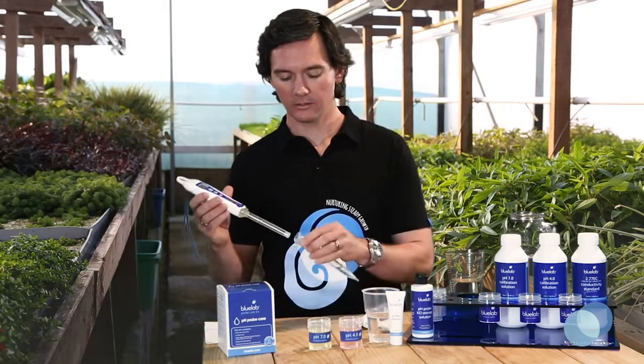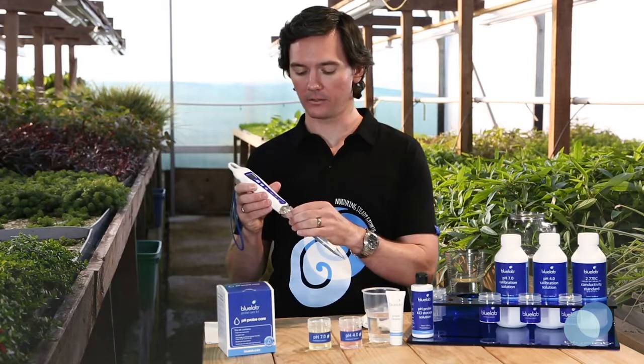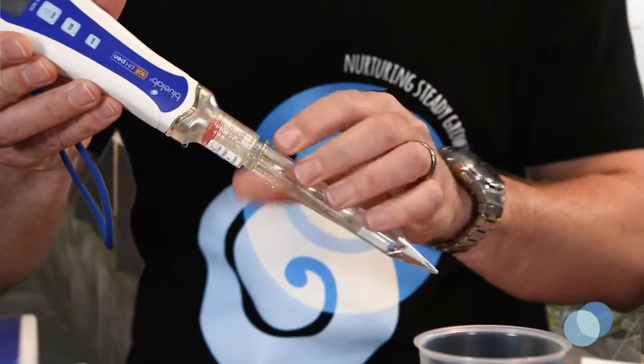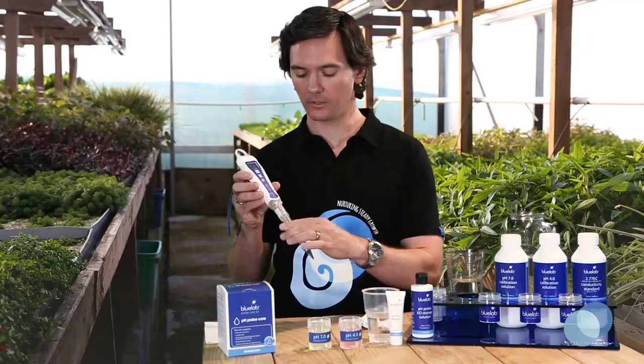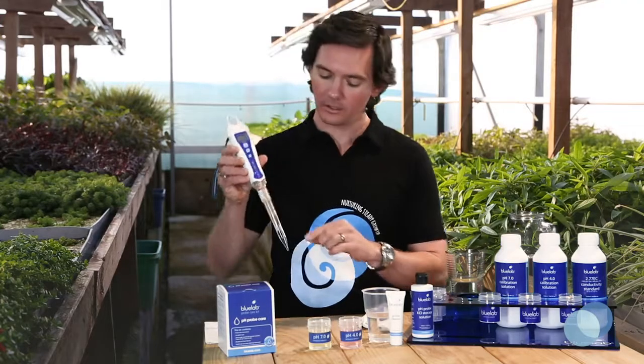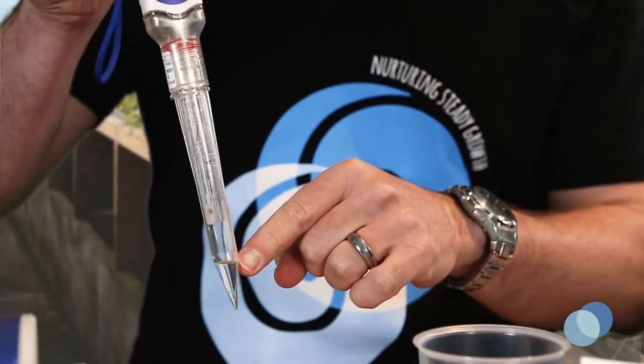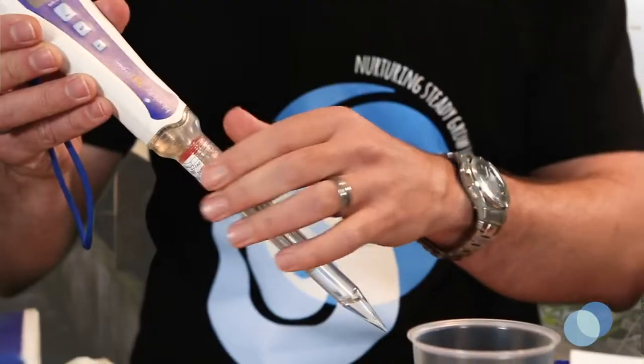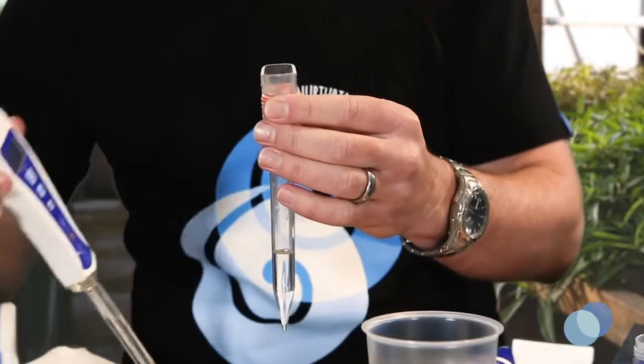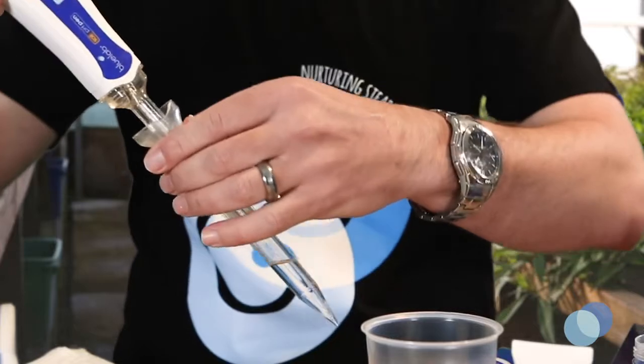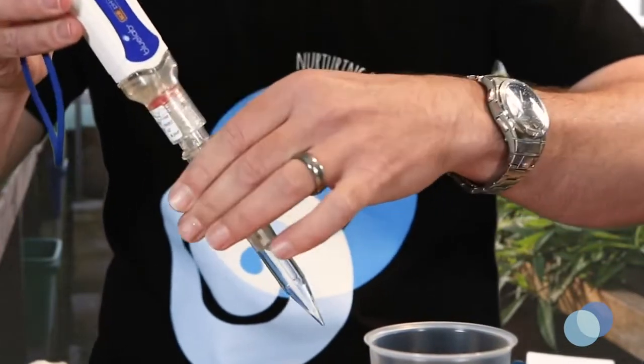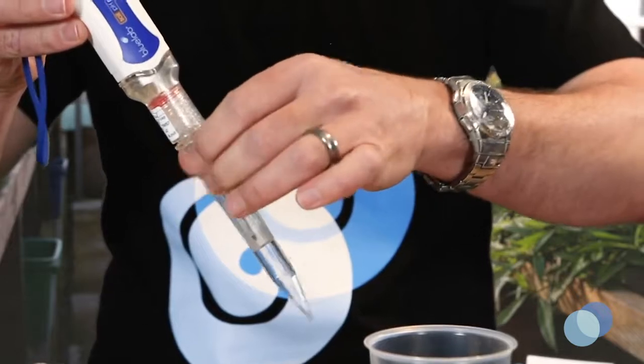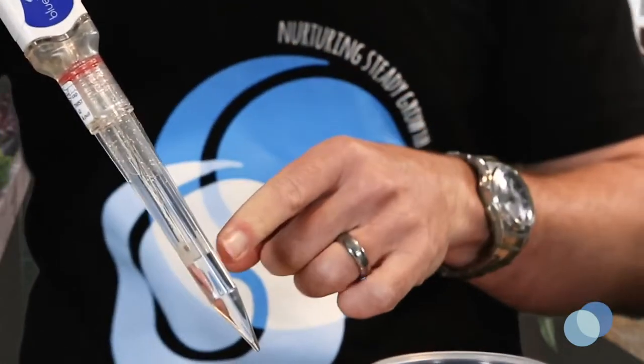To store your Bluelab soil pH pen, gently slide the probe cover back on the pen until it touches the body. Carefully screw the dibber into the storage cap until it's sealed, but not too tight. Check that there's enough KCl storage solution inside the storage cap to fully cover the probe tip when it's closed. If not, remove the storage cap and add a few drops of KCl storage solution and replace the cap. Then you're ready to store your probe.